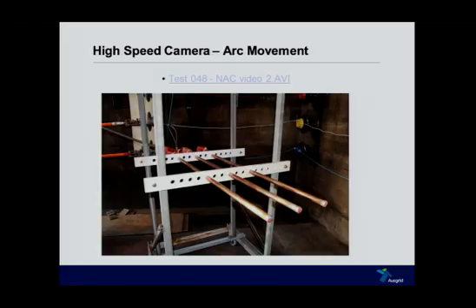This first high-speed video shows the movement of the arc along the electrodes. Normally we tie the fuse wire along the end of the electrodes, but this time we tied it to initiate the arc further back. In real time, this video takes 30 milliseconds.